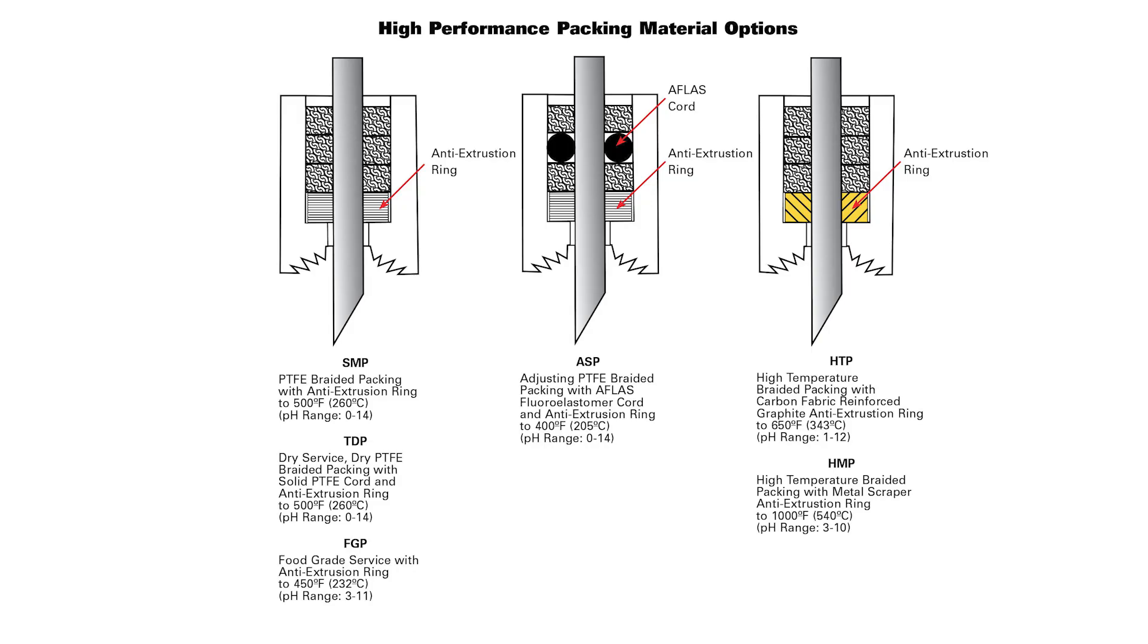DeZURIK provides convenient packing kits for each valve size that include the proper components for the high performance packing option in your knife gate valve. Components can include an anti-extrusion ring of PTFE or copper wire scraper, high temperature carbon graphite, square braided packing, and an energized packing cord.